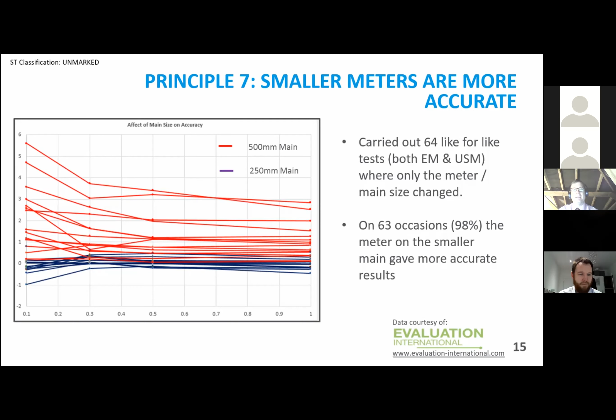Principle 8, very quickly. Some people come to me and say, look, there's an error with the problem. We've got a problem with the meter. We think it's an error. What's wrong with it? And quite often it's actually the SCADA data. Testing done by a UK water company a few years ago did 54 random tests where they looked at the SCADA data, and they then used a data logger, then compared the data.